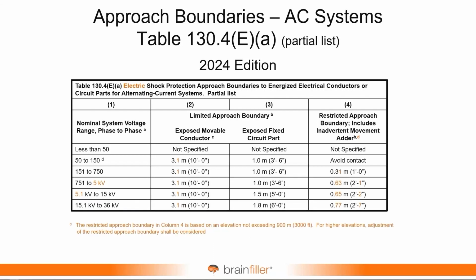So this is what we have today. First off, you notice up at the top, it's not shock protection, it's electric shock protection to adhere to the global change that was made. And these two rows here were actually divided. It used to have 751 volts to 15 kV. Now it's split 751 to 5 kV and 5.1 to 15 kV. This is where the rounding was corrected. So yes, 10 feet is 3.048 meters. Yes, if you properly round it, it's 3.0.